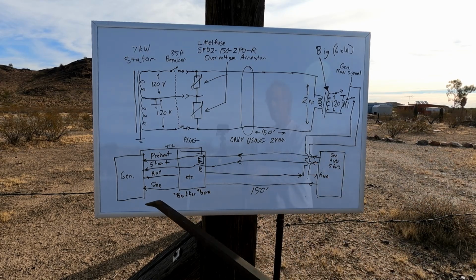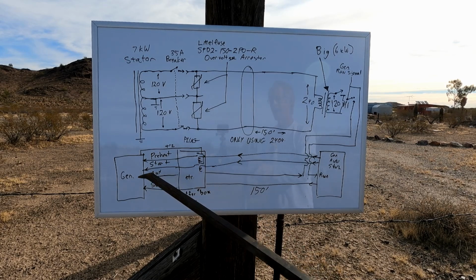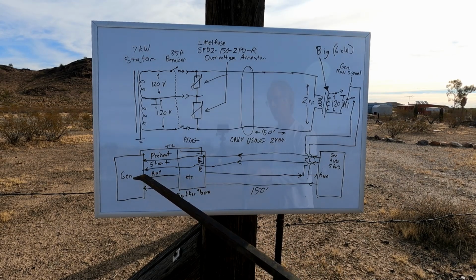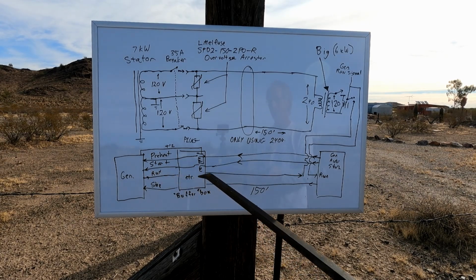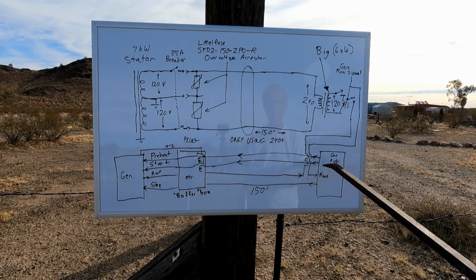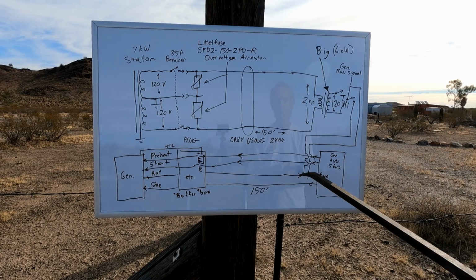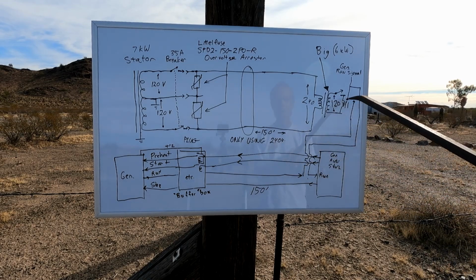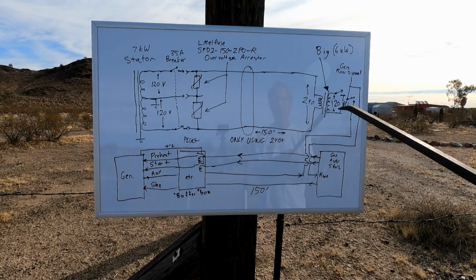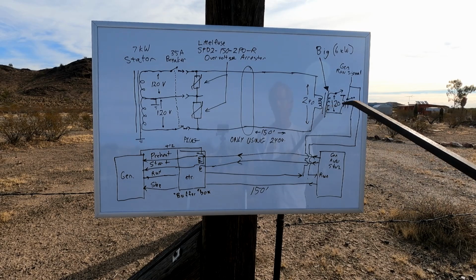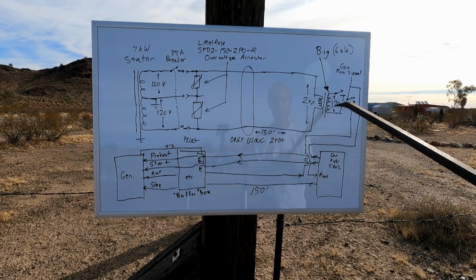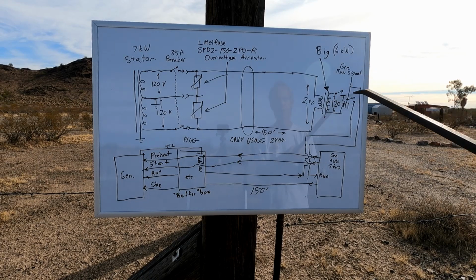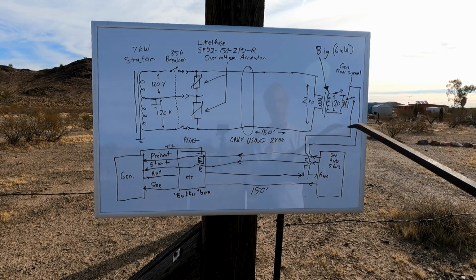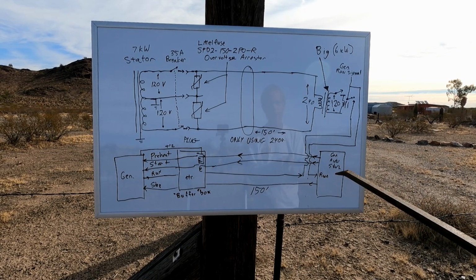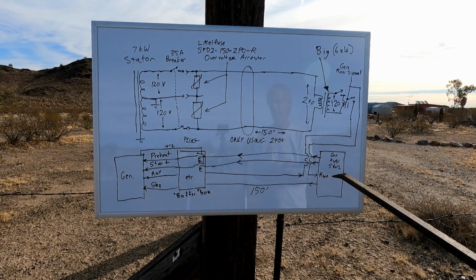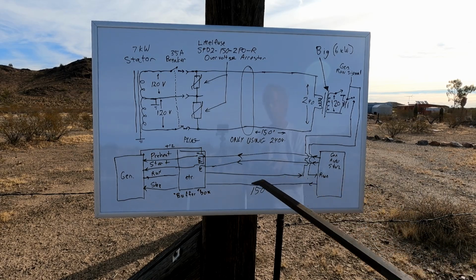And then you get a run signal back from the generator, which actually is related to oil pressure and temperature. The generator will shut itself off for oil pressure or temperature. So this run signal, which is based on that, comes back to the generator auto start to indicate that the generator has stopped. However, the one scenario that it doesn't include is whether or not the AC power drops out, because I need the system to shut the generator down when the power stops at the house, because there's things that can happen in between the generator and the house that can lose that power. So I got a little relay powered off the 120, the generator run signal comes into it, and it comes back out to go into the generator auto start, so that it shuts the generator down if we lose the power. And then the last signal from the auto start is the stop signal.